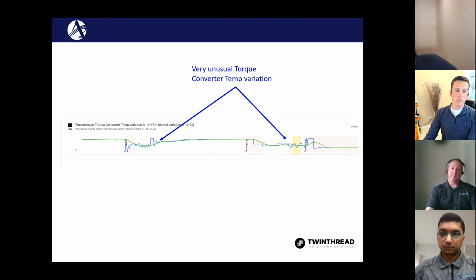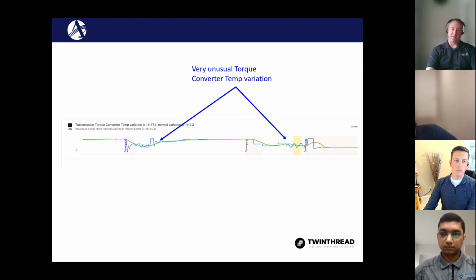Before you continue on with this, I think it's important to just pause for a second, because most of the industry is familiar with condition-based monitoring. That's not new. It's not new to try to set a parameter and monitor that parameter. But what you're saying is that there are times when you don't actually know what the right condition is that you need to be monitoring, which is why it's important to track all of these variables, and then the system will tell you what conditions you need to monitor.